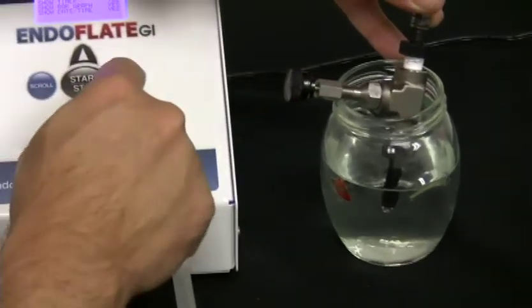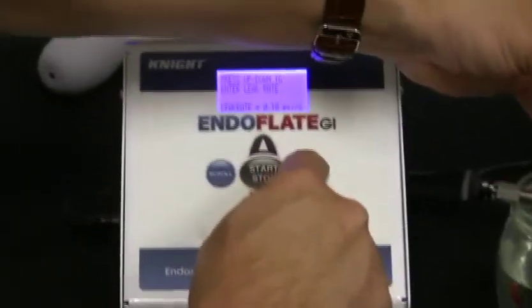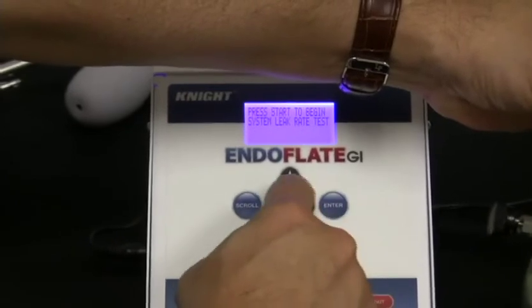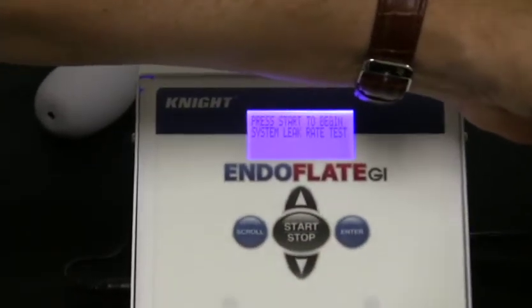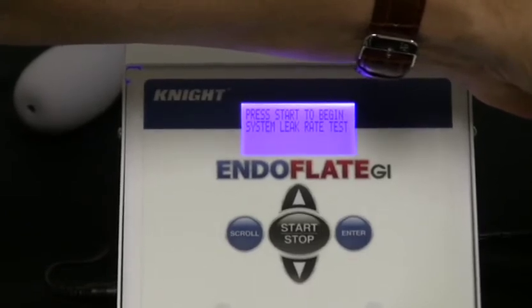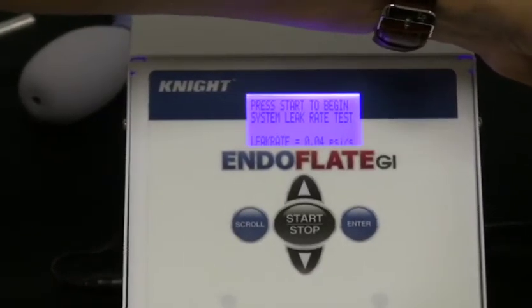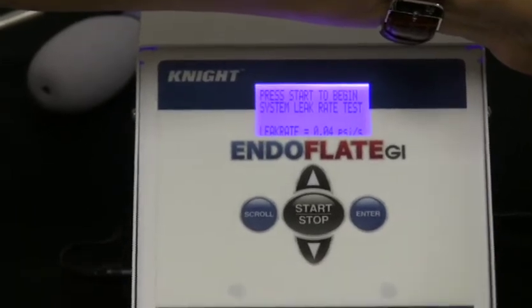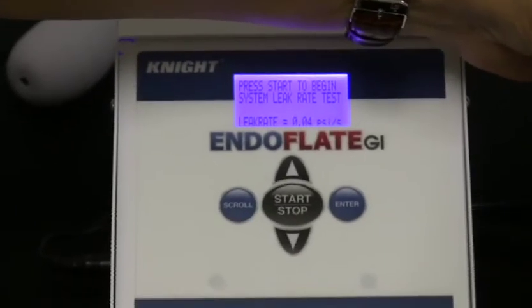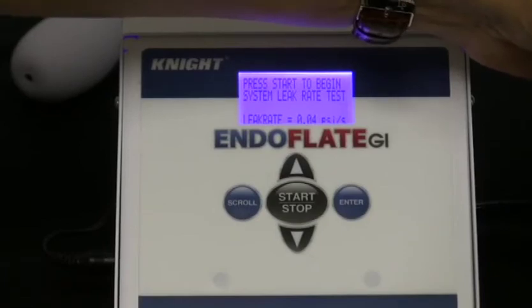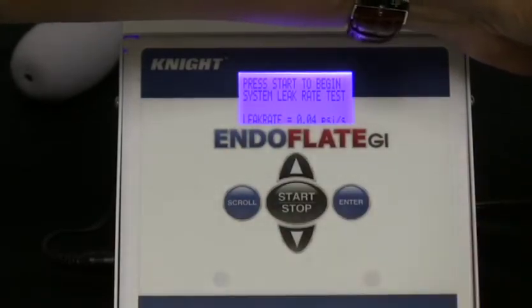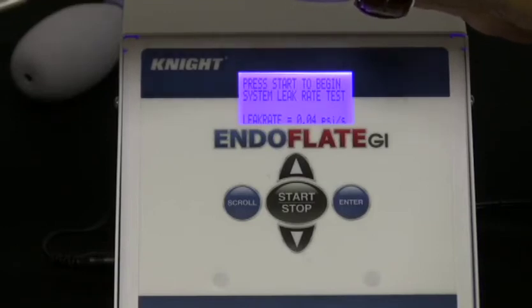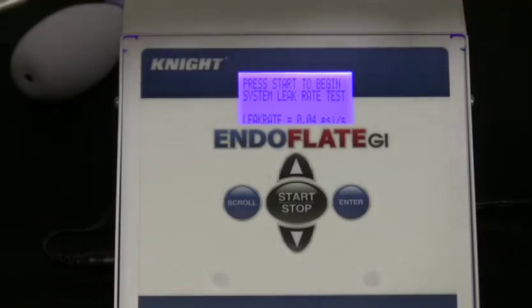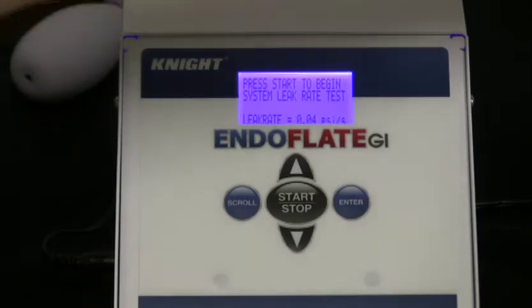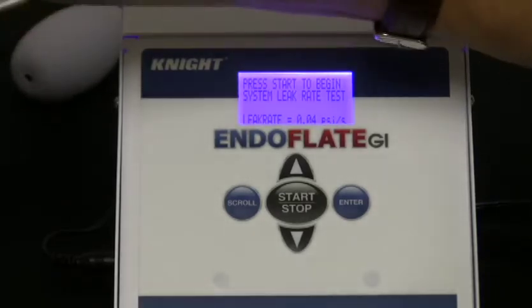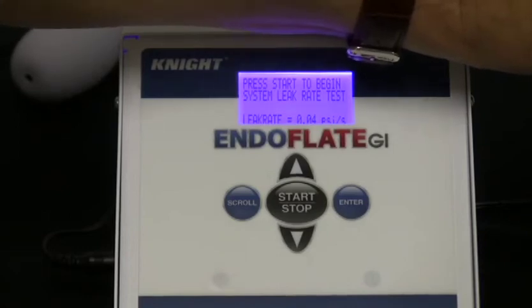I can go back around and show you that same test again. See what the difference is. We were at 0.05. Now we're at 0.04, so not a big change, but again, still a leak. Okay? And with that kind of a setting, you're going to be fine, at least that's what we believe, using that factory setting. And any scope that's got a minimal leak will probably look something like that.